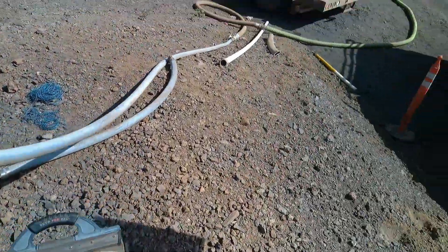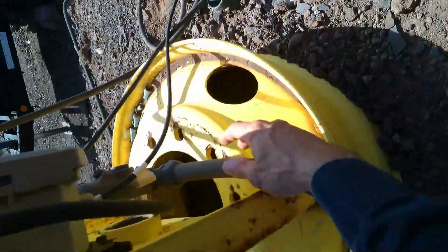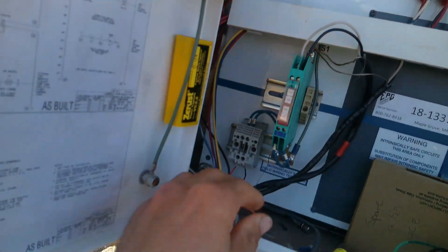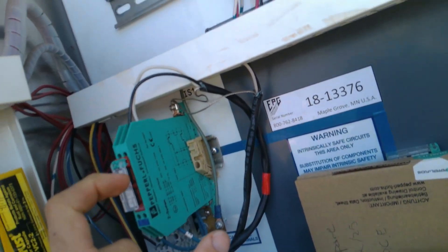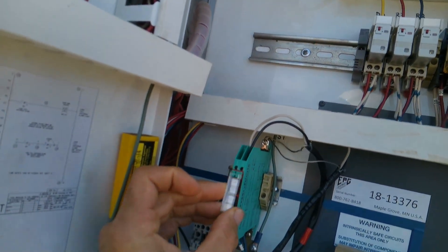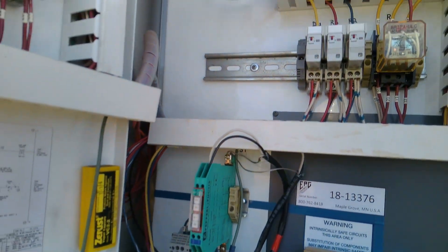Okay, so there's our transducer cable going into our intrinsically safe box, comes around here, comes up and then lands here on this input. It goes through this — what do they call these things — it's got a fuse on it. I think it's an intrinsically safe barrier, just to prevent any arcing. It's got 50 milliamp fuses on it. Let's check all those connections.